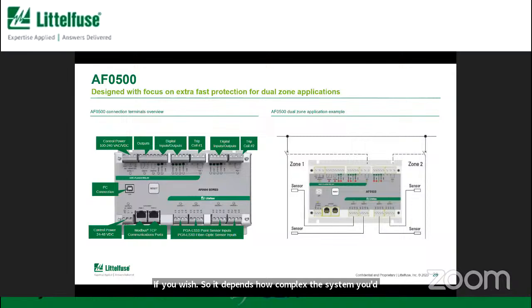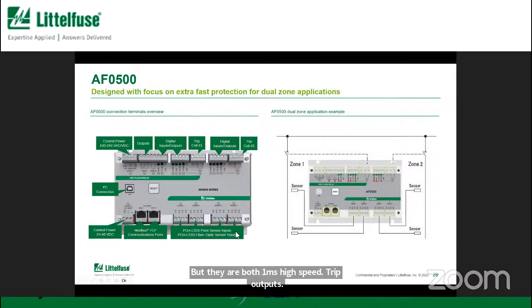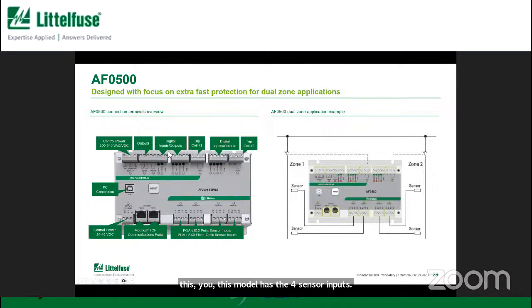The AF500 is the next product in the series. And this product has 2 outputs, but they are both 1 millisecond high-speed trip outputs. And this model has 4 sensor inputs. Again, you can connect multiple units together with this digital I/O. But the other unique function about this product, other than the 2 high-speed trips, is the fact that you have Modbus TCP Ethernet communications if that's required.